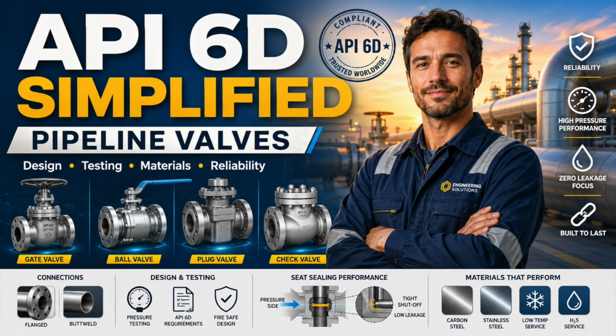If it closes too late, reverse flow builds. When the disc finally closes, the reverse flow is arrested suddenly. That creates slam, surge, and mechanical impact. If the valve operates near an unstable position, it can chatter. Repeated impact can damage the hinge, disc, seat, or retaining parts. For critical systems, check valve selection should be connected to hydraulic transient analysis. A check valve is not passive decoration on a piping and instrumentation diagram.